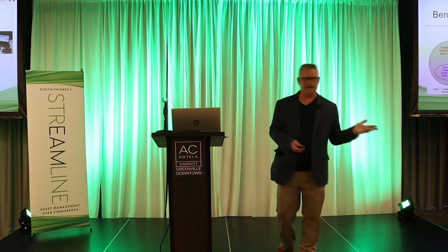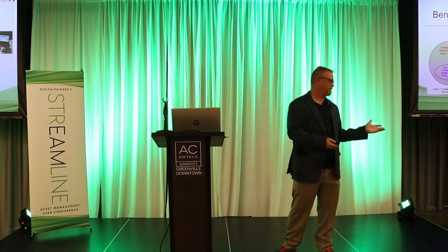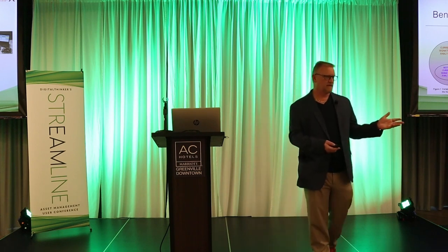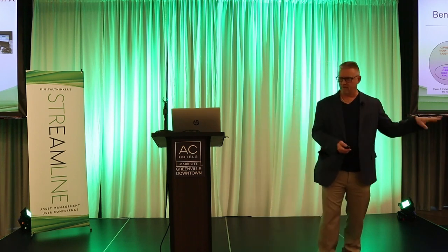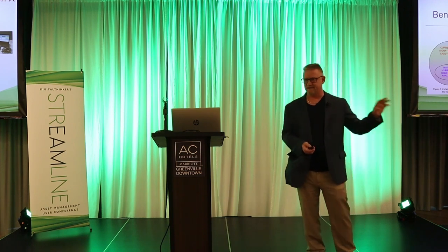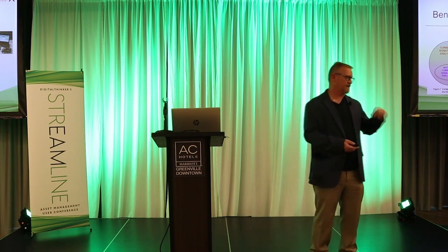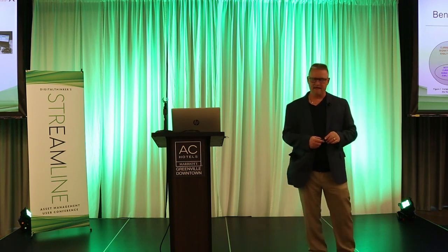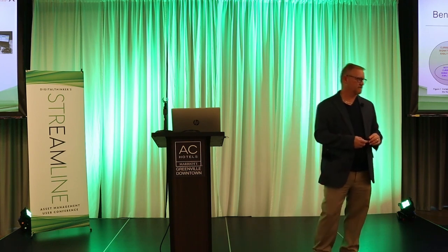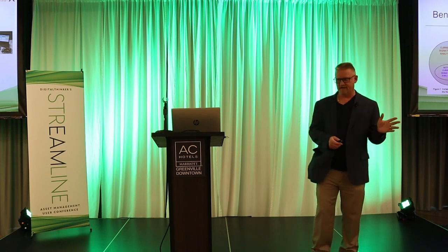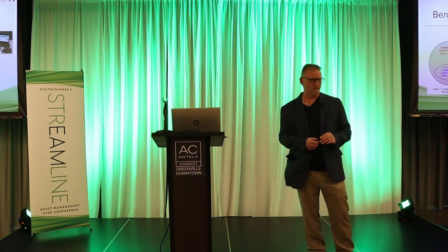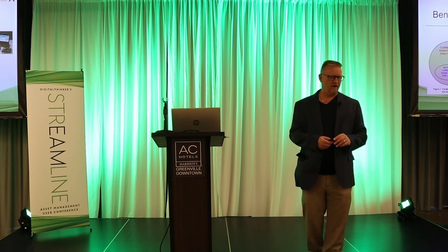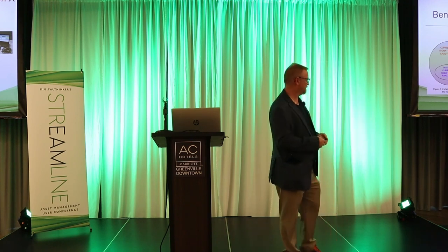This is also a great tool if you have added a bunch of VFDs to your plant. If you have added a bunch of VFDs and you're blowing boards on a regular basis, it's likely that you're not filtering your electricity and you have harmonics back to your substation. And this can find that issue. So if you've installed a bunch of VFDs and you're having issues with boards frying, oftentimes it's harmonics back to the sub.